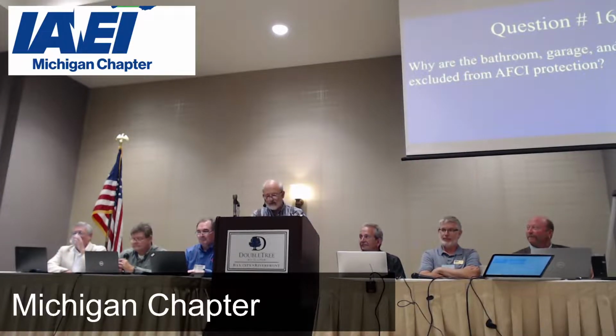All right, Tim, why are the bathroom, garage, and outside excluded from the AFCI protection requirement? Well, the short answer to that is because the industry hasn't completed that evolution yet. And really, it goes back to the Consumer Product Safety Commission back in the early 90s, based on alarming statistics for electrically related fires, as reported by the U.S. Fire Administration. The call for advanced circuit protection came from the CPSC. Consequently, manufacturers in concert with UL developed what we know today as the AFCI.